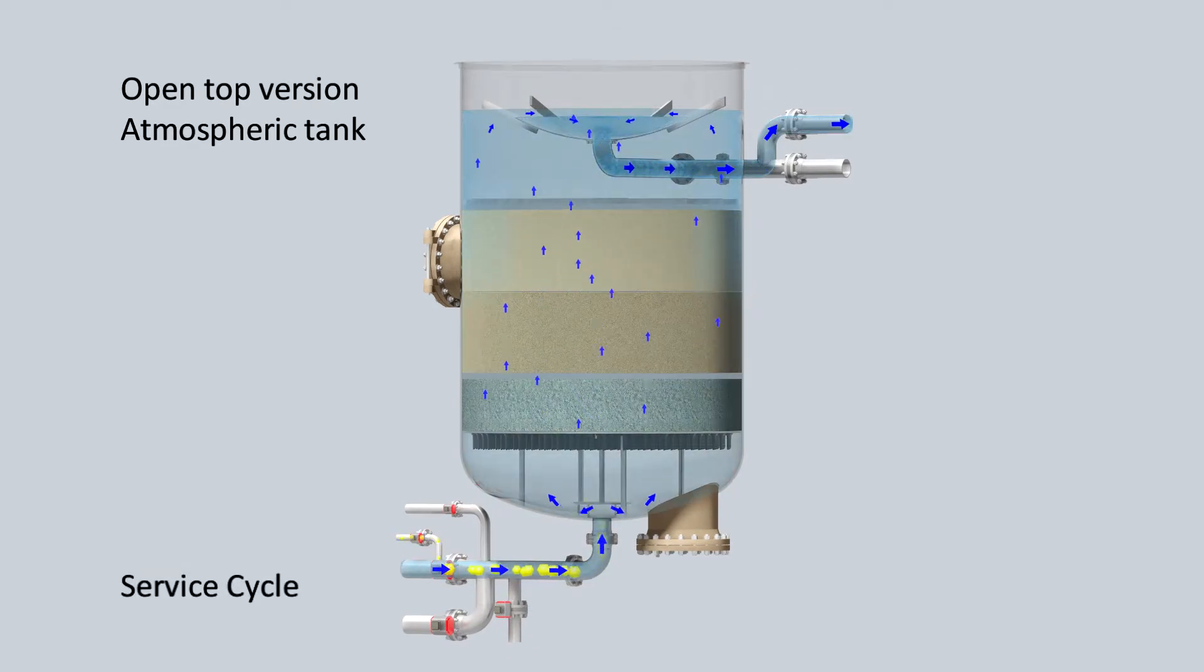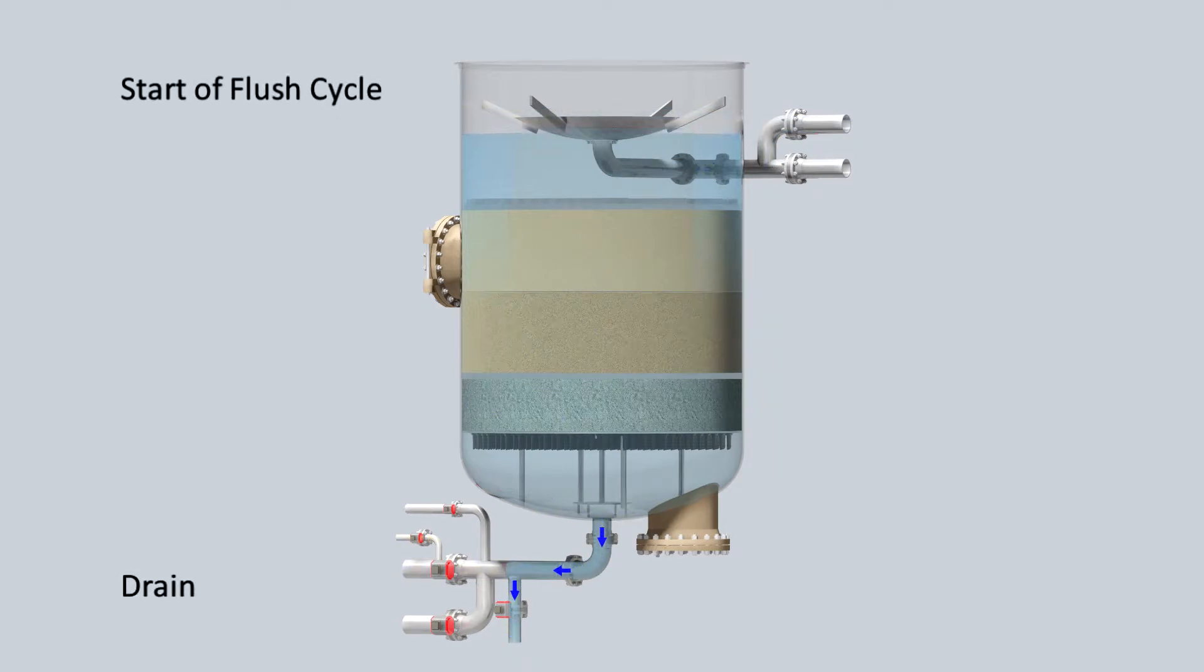During service, as the solids load the bed, the differential pressure increases up to a set point that triggers its cleaning cycle.